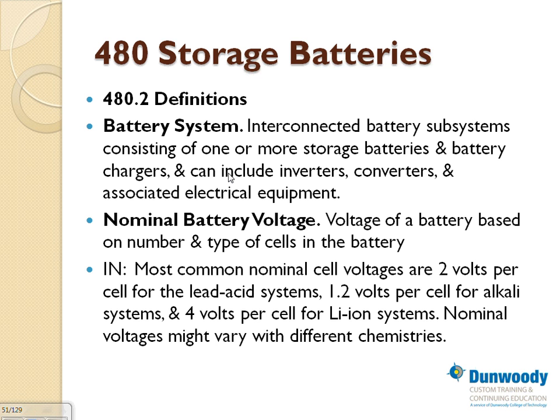Since we use AC primarily in the US and elsewhere, AC is the dominant power system, so you always have to include the inverter and the converter. You convert to DC and you invert back to AC. That's always what we do: battery charger, inverter, converter, all together. Like in data centers, as you know, you have your UPS system. You bring in the AC, convert it to DC, tie your DC battery in it so you can store it for 15 minutes, and then you invert it back to AC and dump it across your servers. Upon the loss of power, you have 15 minutes to shut down your system safely or start your generator back up.